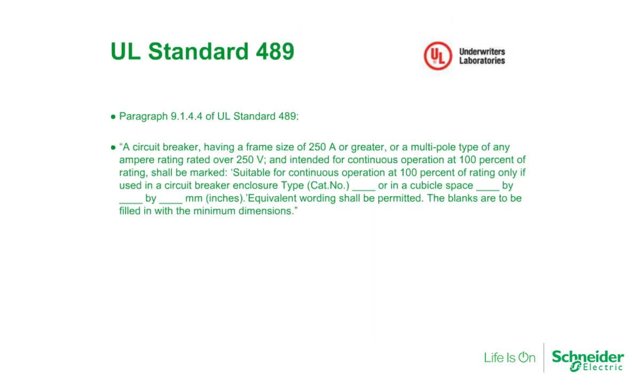When applying 100% rated circuit breakers, there are several UL and NEC restrictions which must be kept in mind. If any of these restrictions are not met, the 100% rated circuit breaker becomes standard and must be applied at the sum of the non-continuous loads plus 125% of the continuous load.